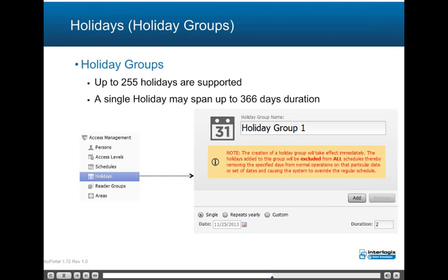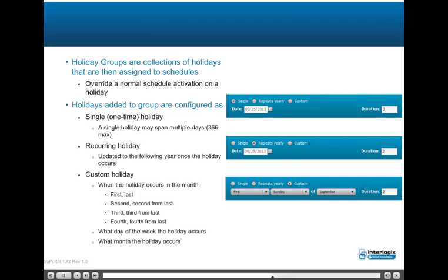A holiday group allows up to 255 holidays. A single holiday may span up to 366 days in duration. Holiday groups are collections of holidays that are then assigned to schedules; holidays override a normal schedule activation on a holiday. Holidays added to a group may be configured as a single one-time holiday (possibly spanning multiple days up to 366 days), a recurring holiday (updated to the following year once the holiday occurs), or a custom holiday where configuration includes when the holiday occurs in the month (first, last, second, second-from-last, third, third-from-last, fourth, fourth-from-last), what day of the week, and what month.